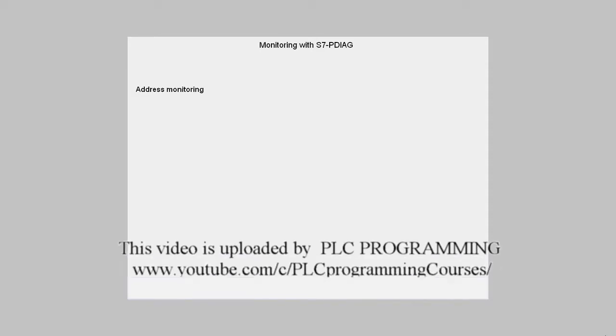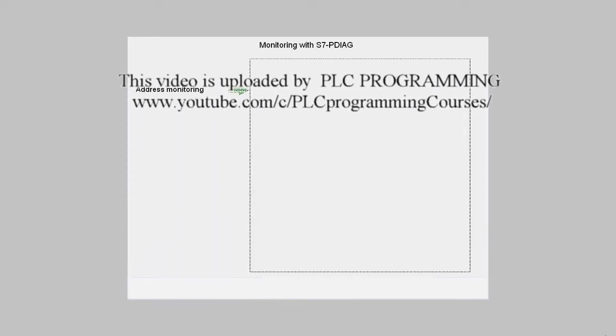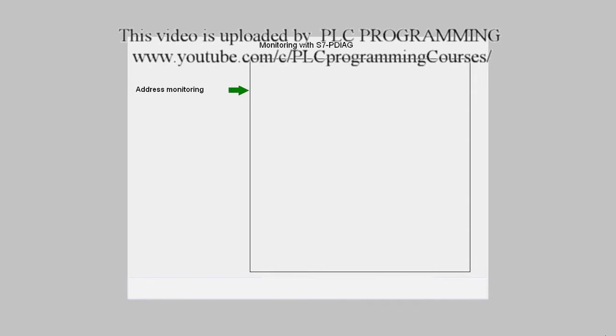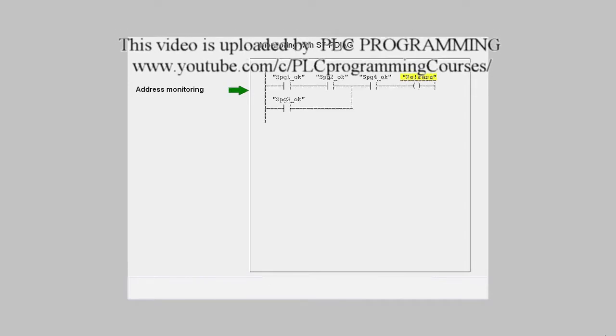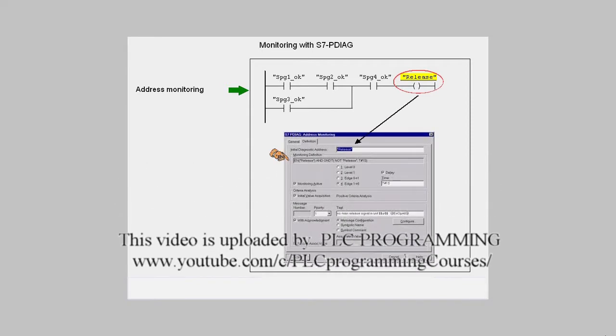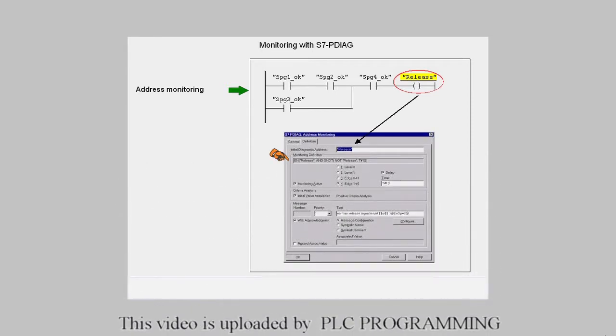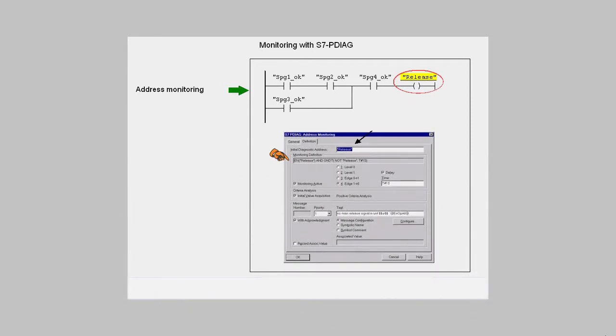The task of the configurator is to attach the error definition to an assignment in the desired network and to parameterize the predefined monitoring logic in a dialog. You have a choice here of edge or level monitoring, combined in each case with a delay time.